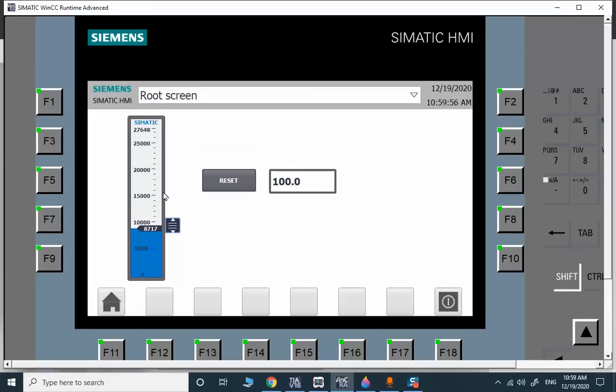And you can see that even if we are in the normal range, the output remains the safe value, and the operator should press the reset to return to the normal value. So in case of error, and if the cause of error is gone, operator intervention is crucial.